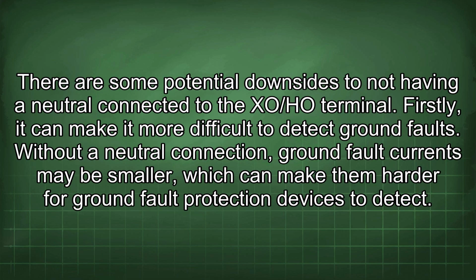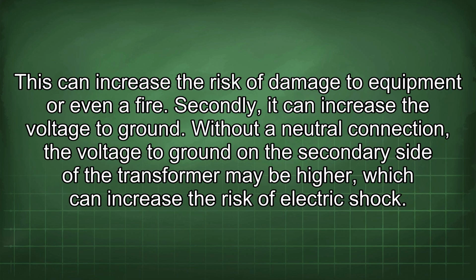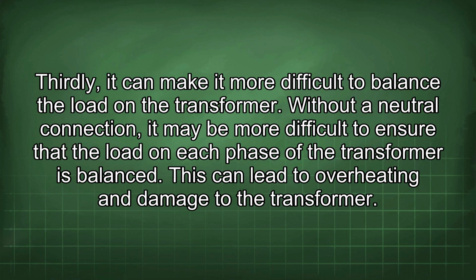There are some potential downsides to not having a neutral connected to the XO/HO terminal. Firstly, it can make it more difficult to detect ground faults. Without a neutral connection, ground fault currents may be smaller, which can make them harder for ground fault protection devices to detect. This can increase the risk of damage to equipment or even a fire. Secondly, it can increase the voltage to ground. Without a neutral connection, the voltage to ground on the secondary side of the transformer may be higher, which can increase the risk of electric shock. Thirdly, it can make it more difficult to balance the load on the transformer. Without a neutral connection, it may be more difficult to ensure that the load on each phase of the transformer is balanced. This can lead to overheating and damage to the transformer.